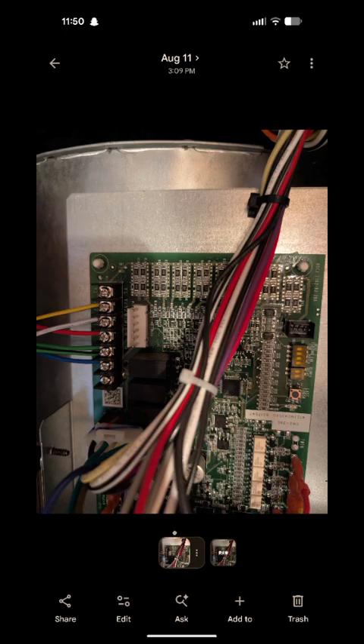This is just showing you the wiring. If you go back and look at the pictures I've put here, I'm showing you how they're meant to be wired for the situation where you're dual fuel and you have an A2L for your cooling or heat pump. This one is straight cool. That's one of the typical problems we see on A2L wiring in terms of dual fuel.